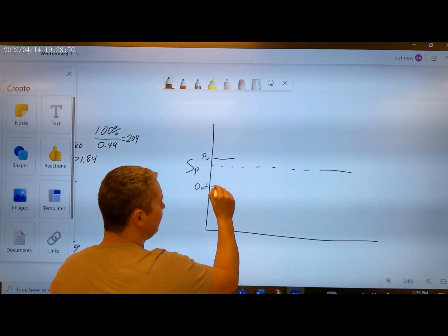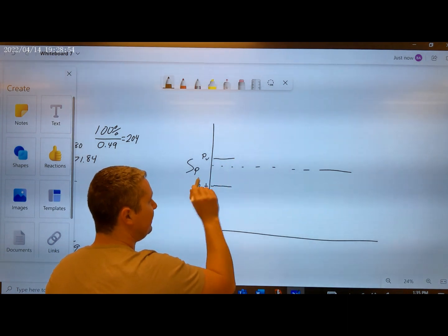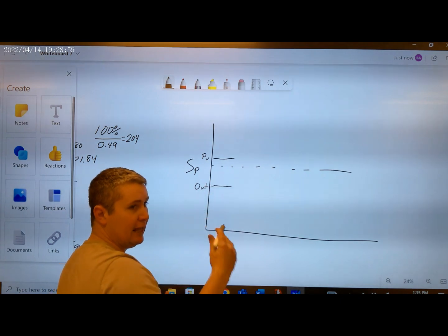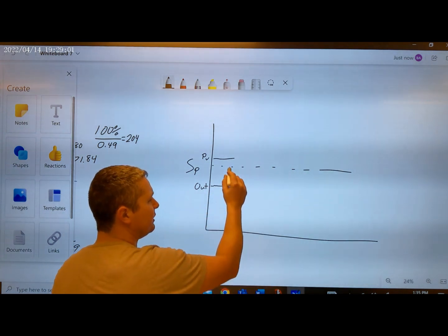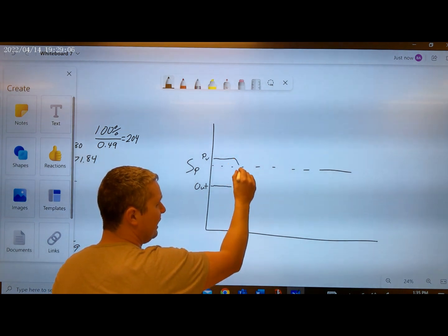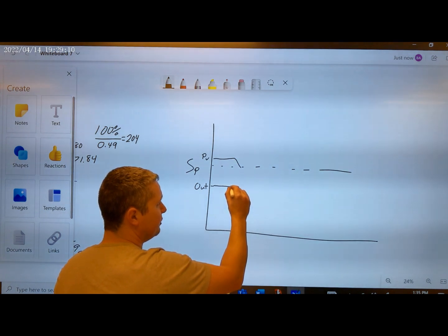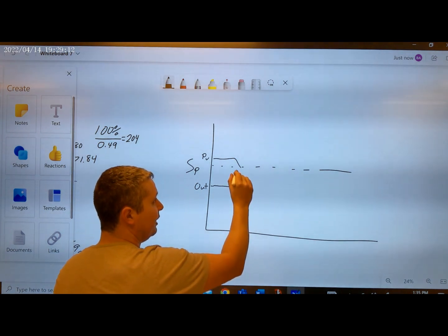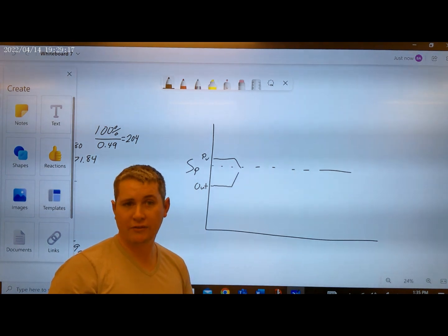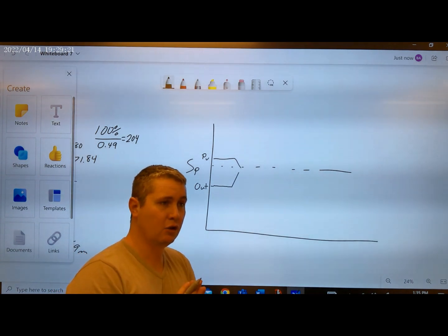If your output is coming along because your process variable is just going along steady, this is your proportional band, or your proportional gain, right? Your proportional gain is giving you this output. As soon as you get a ramp of any kind, if this is reverse acting, it's going to jump, not just proportionally, but derivatively. Derivative means that it's going to the slope.